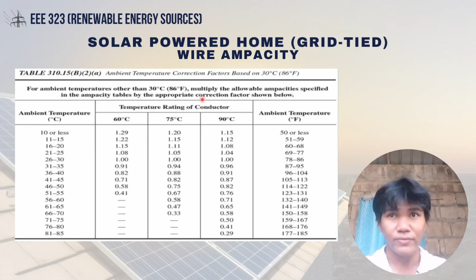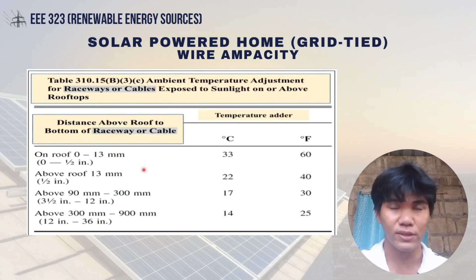Table 310.15(B)(3)(c). Yun yung for ambient temperature adjustment for raceways or cables exposed to sunlight on or above rooftops. Dito po nakabase yung cables kung ito ay exposed sa sunlight, nasa bubong. May distance dito na above roof to bottom of raceways: 13 mm or 1/2 inch, above 13 mm to 90 mm or 1/2 inch to 3 1/2 inch, above 90 mm to 300 mm or 3 1/2 inch to 12 inch, above 300 mm to 900 mm or 12 inch to 36 inch. Dito rin po yung added temperature na pwedeng magamit.